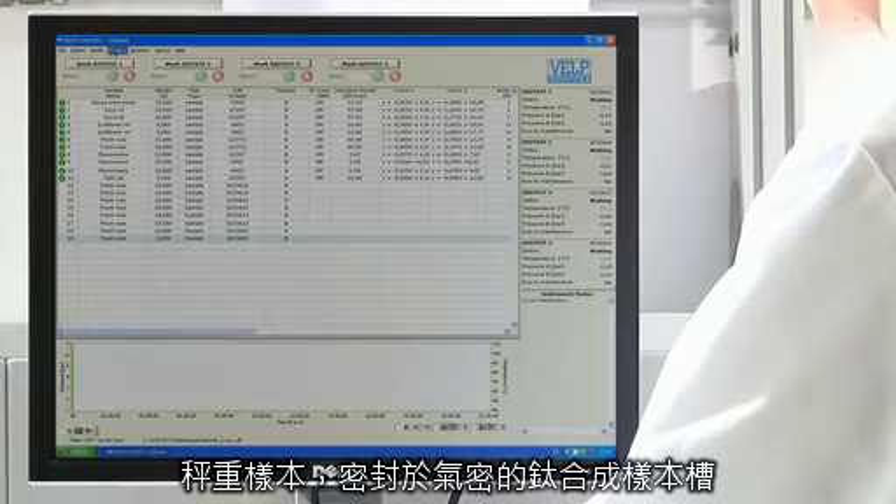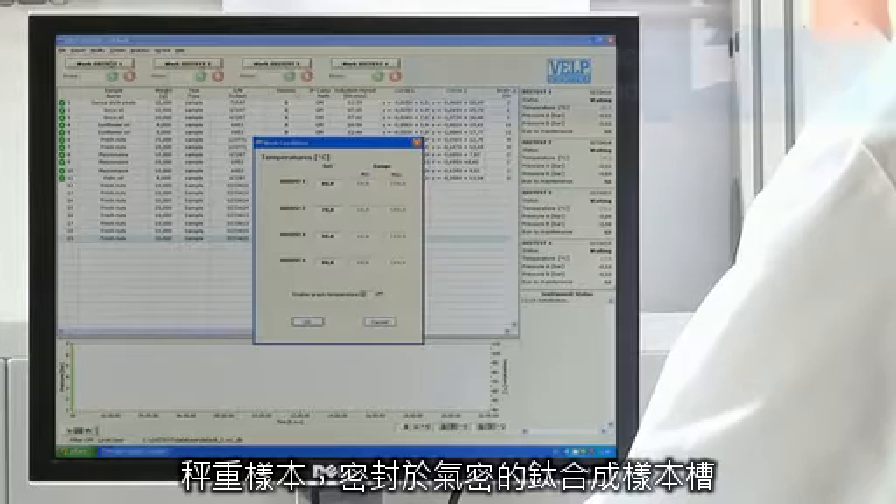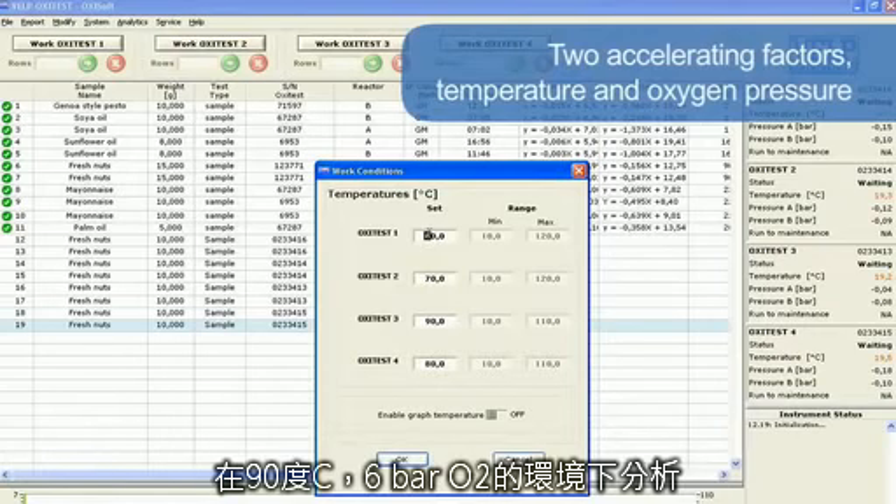The Oxitest speeds up the oxidation process because of two accelerating factors: temperature and oxygen pressure, usually set at 90 degrees centigrade and 6 bars, according to the most common applications.